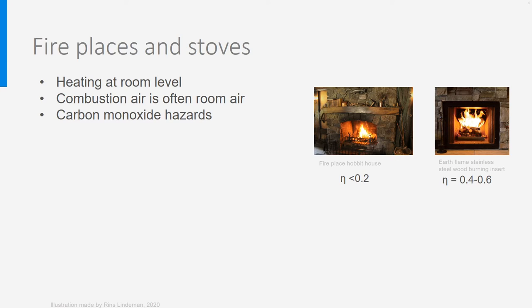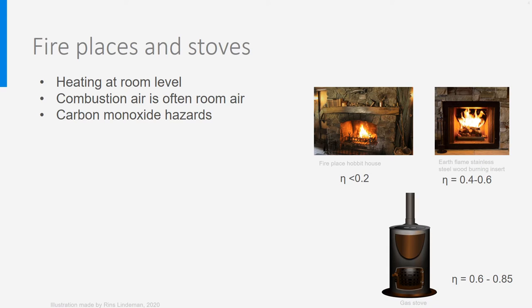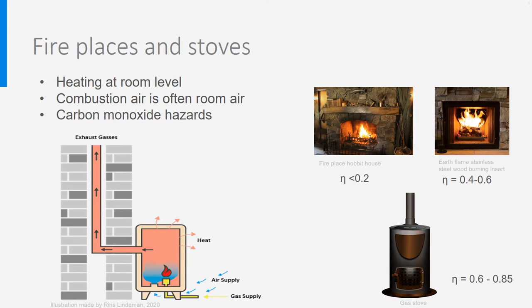Next to wood stoves, there are also coal and gas stoves. They are generally placed in the room away from the walls, by which a larger part of the heat produced ends into the room by convection or radiation. Such gas and coal stoves may have an efficiency between 60 and 85%. Just like for wood stoves, air is taken from the room, so good ventilation is needed.